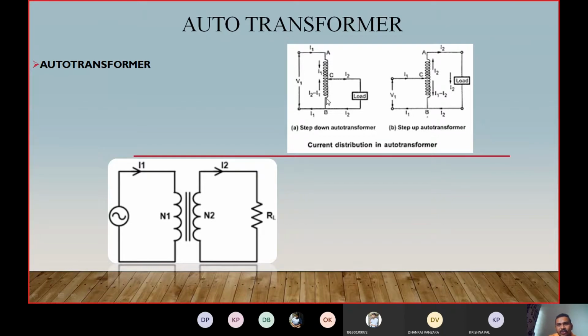But look at this auto transformer circuit. Here, the primary and secondary windings are connected both electrically and magnetically. There is no isolation between primary and secondary winding here, whereas in the two winding transformer there is isolation between them. This is the main difference. In auto transformer there is a single winding, whereas the two winding transformer has two separate windings. In auto transformer, some part of this single winding works as the primary and some part works as the secondary.